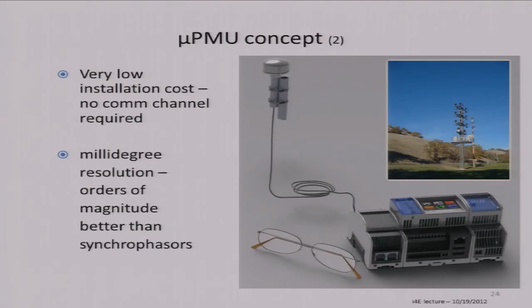A really critical point—a big cost in phasor measurement unit installations—is the communication channel that has to stay open constantly back to the phasor data concentrator, and that's not inexpensive since it has to run constantly and carry a large amount of data. Getting that kind of communication channel on a distribution system would be very difficult, so we've designed this so we don't need one. We've also done a lot of work, with patents still in progress, to get millidegree resolution instead of a degree or a tenth of a degree, which is what it will take to measure this kind of data on distribution systems.